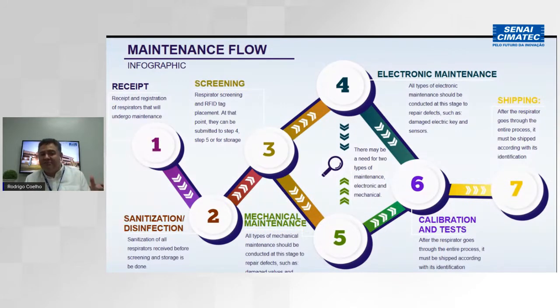On the electronic maintenance, as I mentioned, we have some guidance already, and the experience from the previous machines that arrived here says that those maintenance usually involve batteries or some kind of soldering of the wires on the electronic components and so on that need to be replaced or repaired. Afterwards, as was already mentioned, I need to go to step 6, where I will do the calibration and the tests of the equipment after the maintenance. And here we must, most of the time, I would say 30%, 35%, return the equipment to do a kind of fine adjustment, fine maintenance, to ensure that the equipment is working properly. Okay, this is necessary before I start to clean again my machine, clean again the whole pieces of my equipment, to finally pack everything and ship back to the hospital.